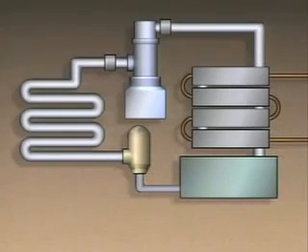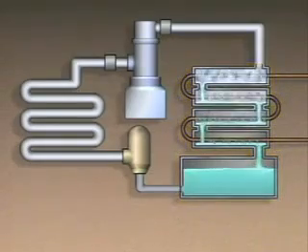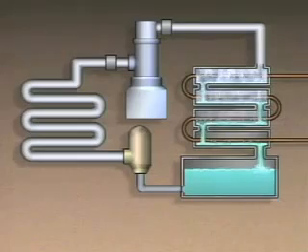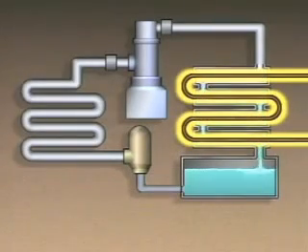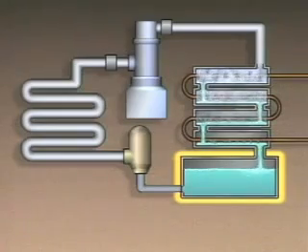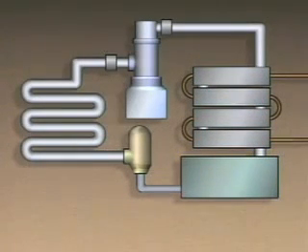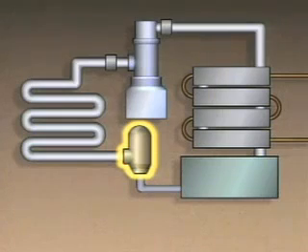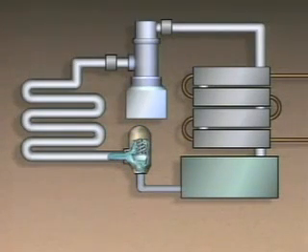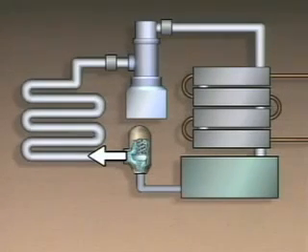The component in which heat is rejected from the cycle is a condenser. In the condenser, the refrigerant vapor is condensed back into a liquid, and as it flows through, it gives off heat. A cooling fluid — usually air or water — receives heat from the refrigerant. The refrigerant that condenses collects in a receiver, where liquid refrigerant is stored until it flows into the expansion step. The expansion step is carried out by an expansion valve, which controls the expansion of the refrigerant and its flow to the evaporator. As the refrigerant passes through the expansion valve, it expands rapidly, causing its pressure and temperature to drop, so the fluid flowing into the evaporator is a low-pressure, low-temperature liquid.